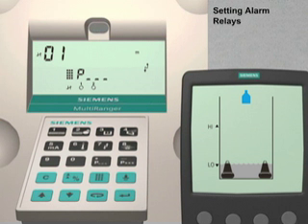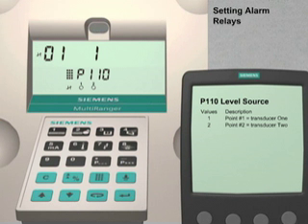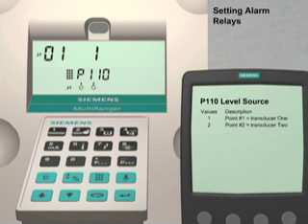The first parameter is parameter 110. Enter 110. This parameter sets the level source controller for the alarm relays. The level source controller for the alarm relays will be transducer number 1. The Multiranger display is currently showing that the level source controller for relay number 1 is transducer number 1. The single digit above the parameter number field is the index value, currently showing 1, which represents transducer number 1. The pair of digits in the upper left of the LCD is the index number, currently showing 01, which represents relay number 1.